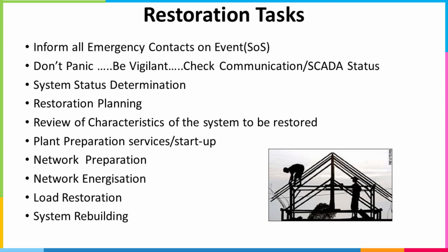Then you prepare your network. Okay, the power is available, the black start capable generation has started. Then you prepare your network and slowly you energize your network and take the loads in service, maintain the load generation frequency in that particular island or wherever you are getting the supply from, and you start rebuilding the system. So hope you see the picture that is basically depicting the same restoration task.